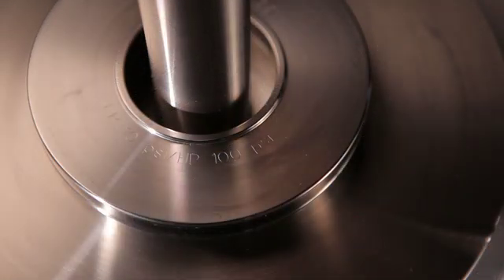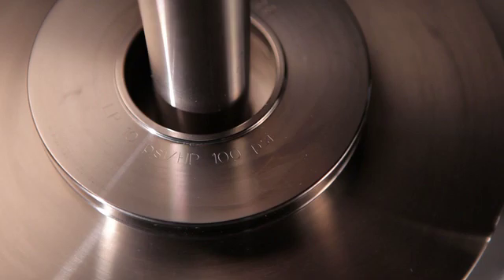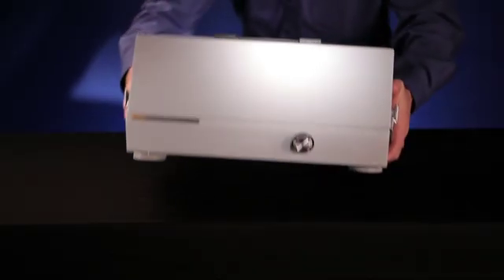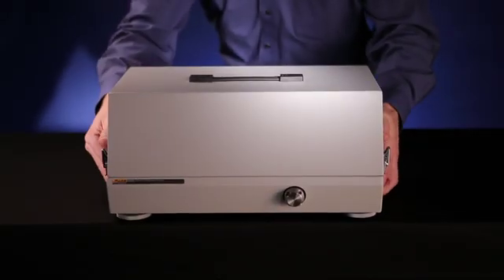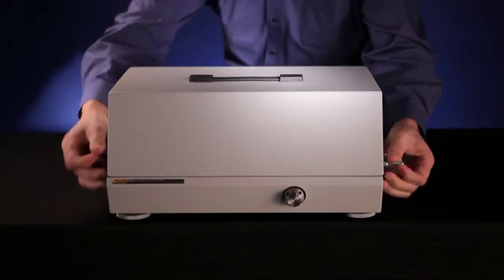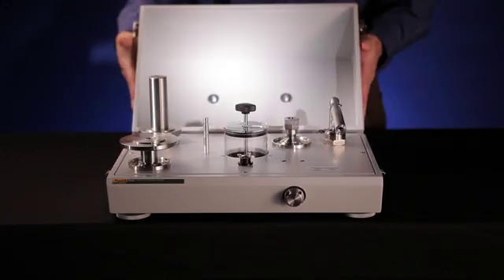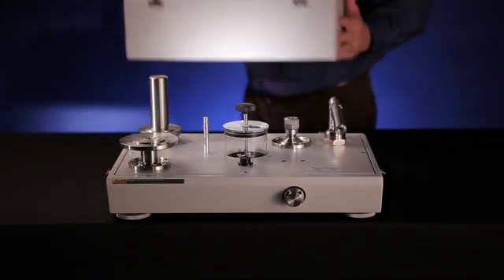During production, the weights are trimmed to provide specific pressure values when used at the provided local gravity and standard environmental conditions. The exact pressures generated are provided on the calibration report. The P3100 series deadweight tester can be set up on any level, stable workbench or similar surface.